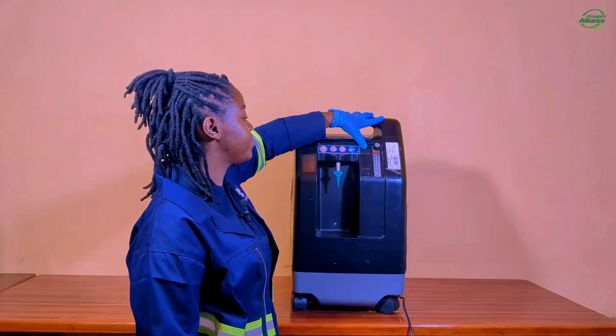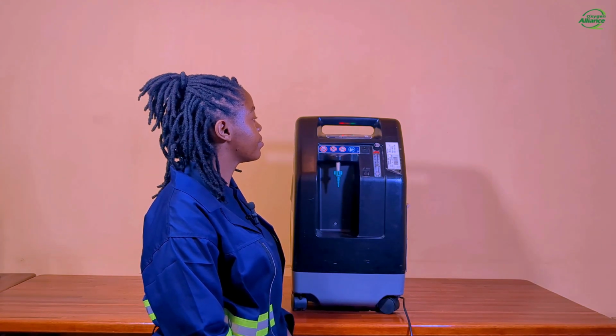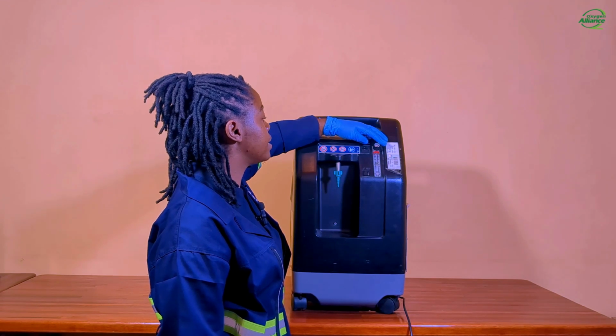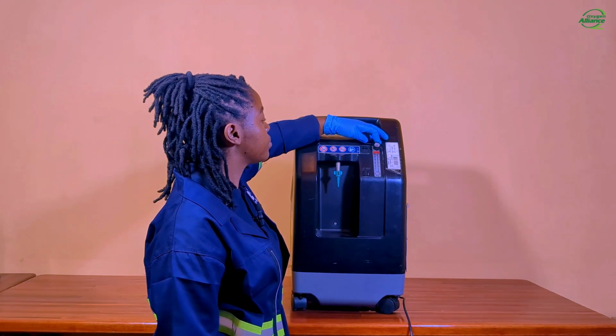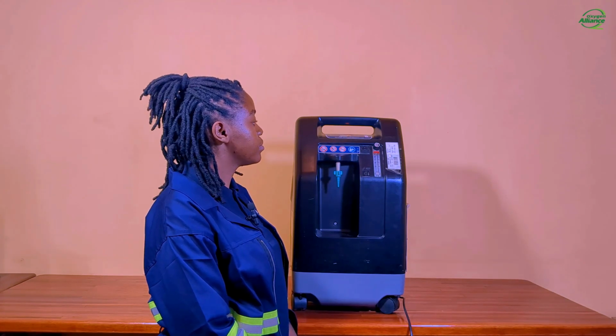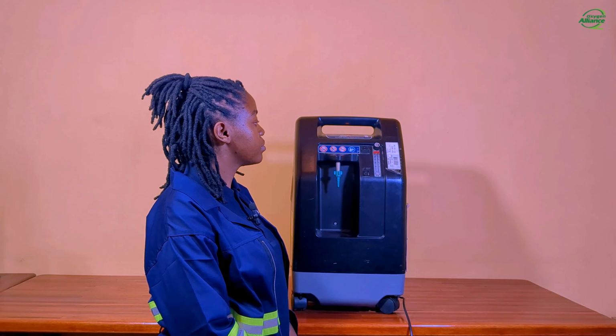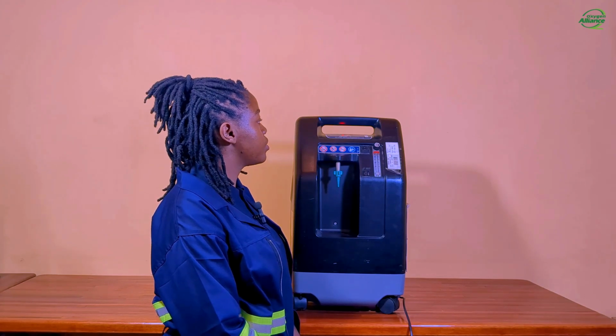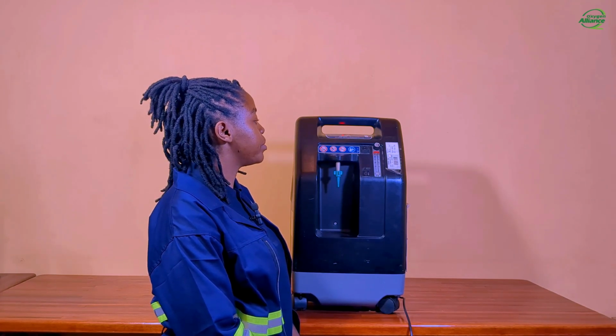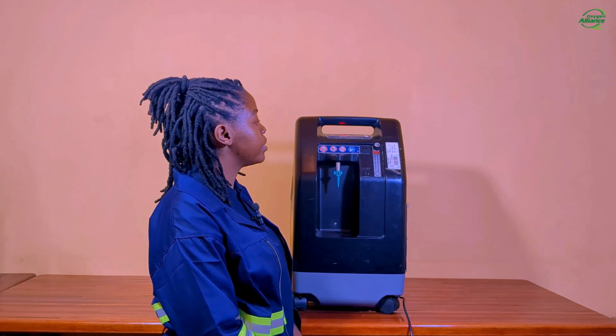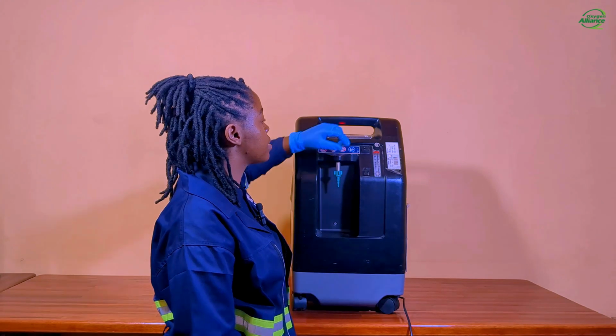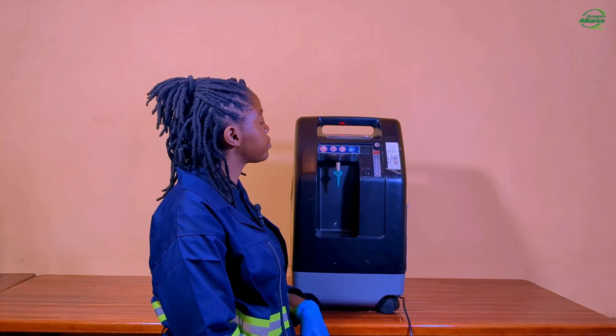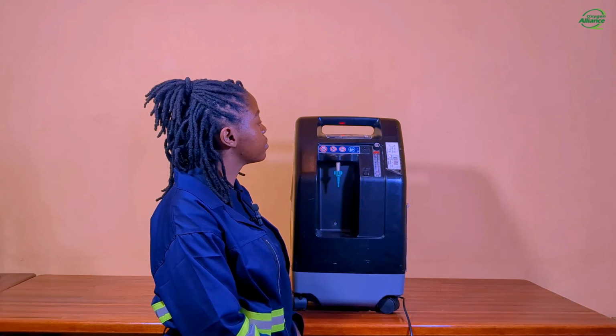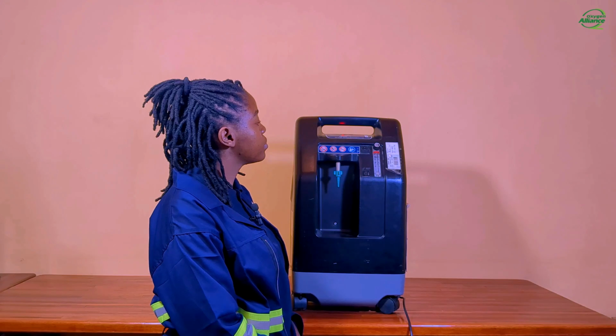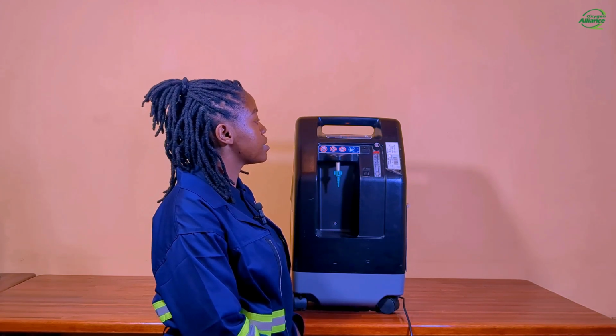So I will turn on the concentrator, and then I will set my flow rate to above 10 liters per minute. And as you can see, the service indicator light has turned on, being accompanied by a beeping sound. And to remove this alarm, I will simply reduce the flow rate to below 10 liters. And that is how you can remove this alarm.